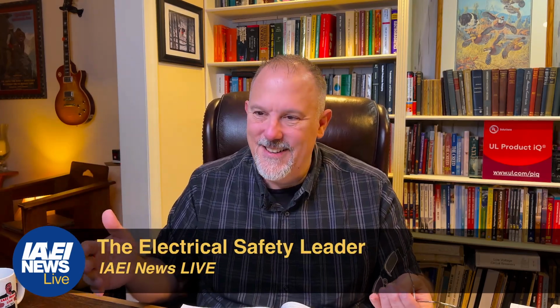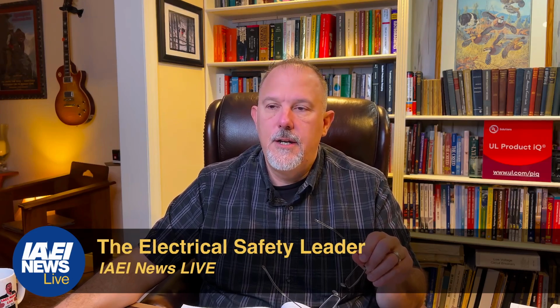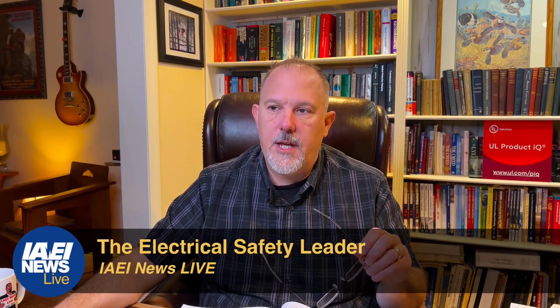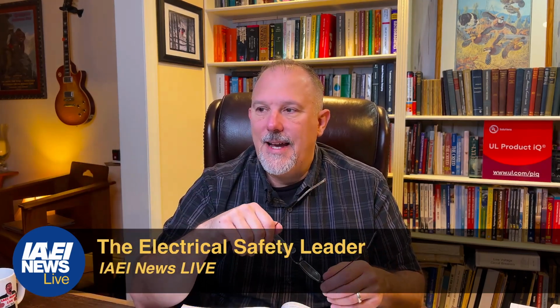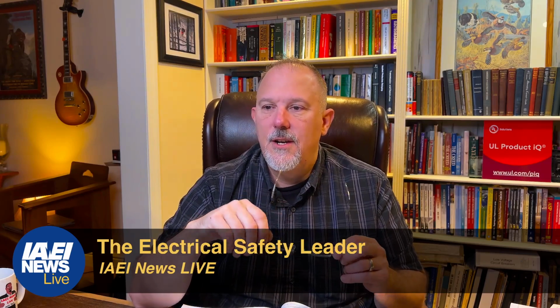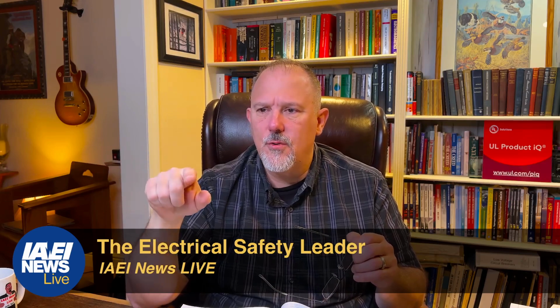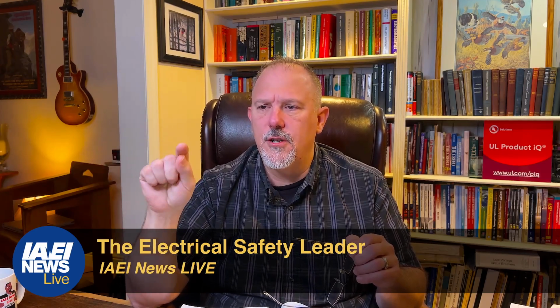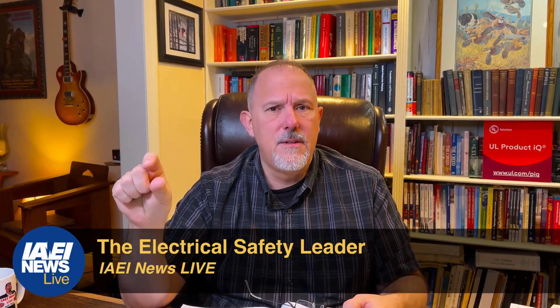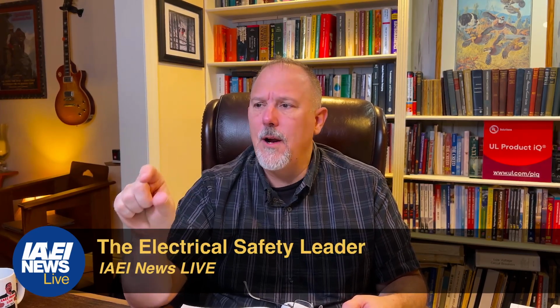Oh my gosh, Eric. But I don't know that striking it from 404.22, I think you'd have to change 404.2, because 404.2 addresses the switch locations. We should just say pull a neutral. But in any case, the exception, that language: the number of electronic control switches on a branch circuit shall not exceed 5. The connection requirement shall not apply to replacement or retrofit. That's the exception. That other sentence, the number of electronic control switches on a branch circuit shall not exceed 5, and the number connected to any feeder on the load side of a system or main bonding jumper shall not exceed 25, that's a requirement. That's not an exception. That's a requirement.